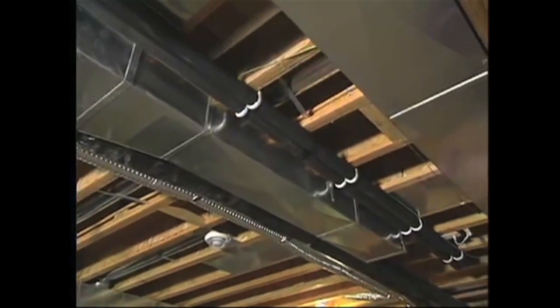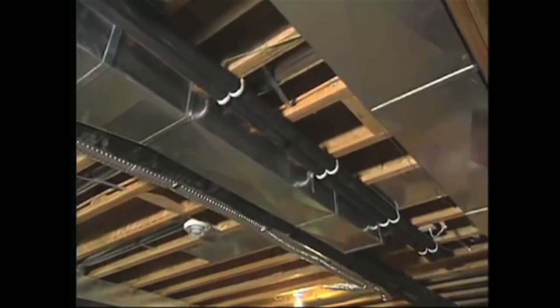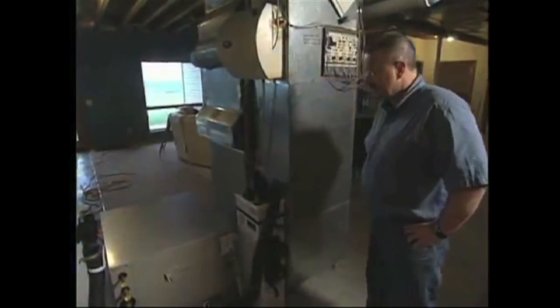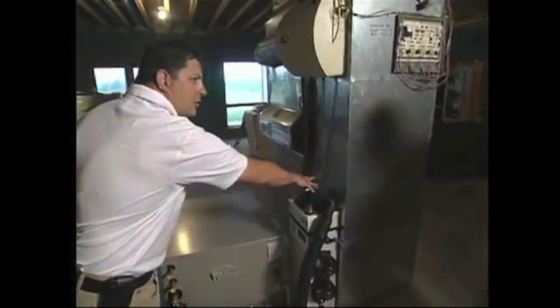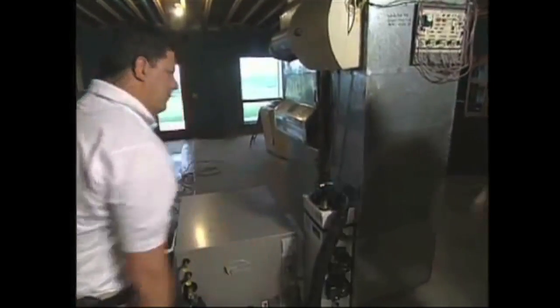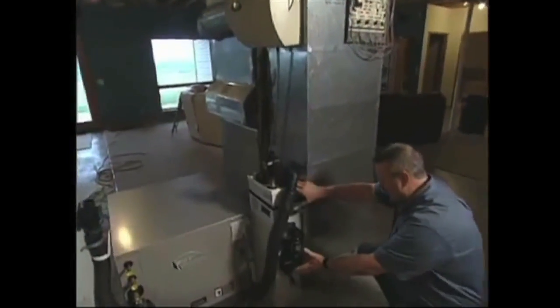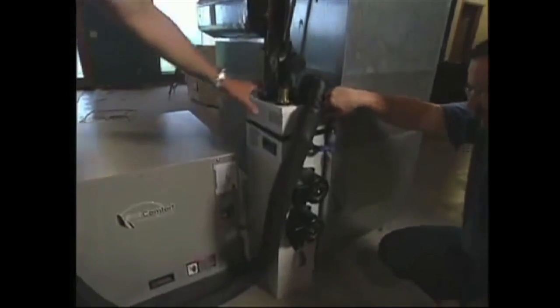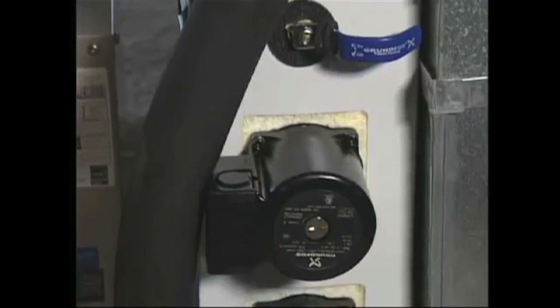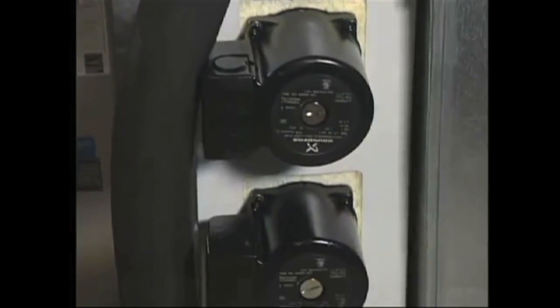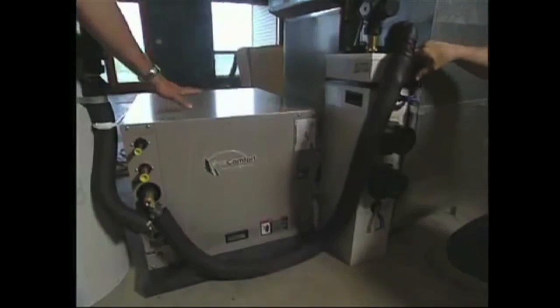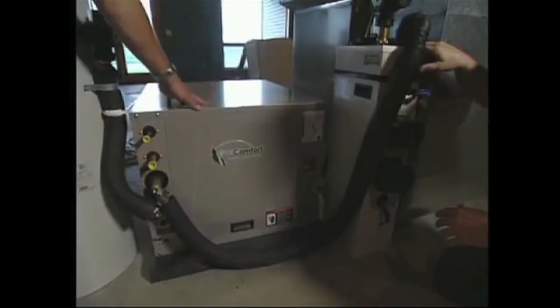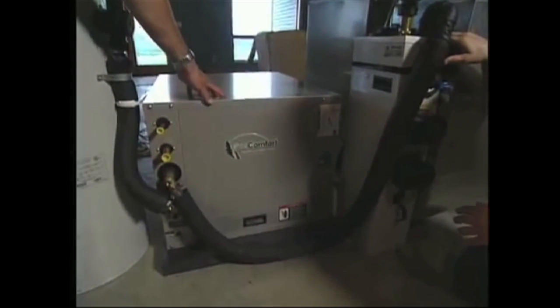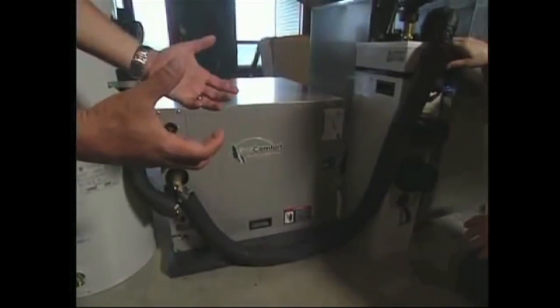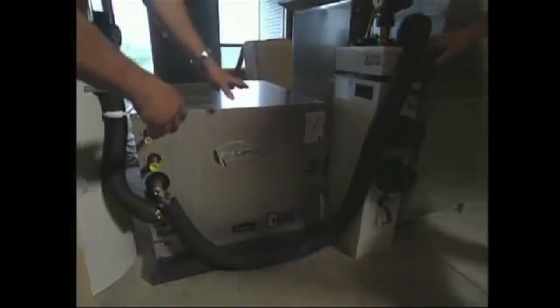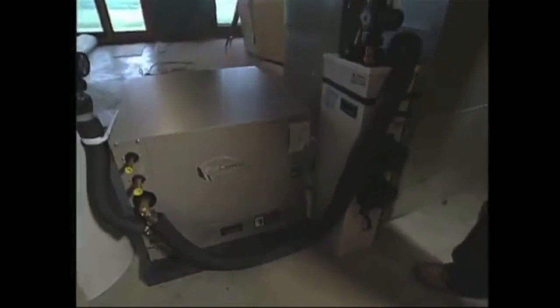I didn't even notice those two pipes there, are they tied into these components? Yeah, one pipe coming in here and one going out. So what am I looking at right here, these would be the circulating pumps? That's right, these move the fluid through the loop field and then through the heat exchanger in the heat pump. And here is the actual heat pump itself, with a compressor inside. This is where we intensify that heat in the heating season and deliver it to the space. Then in the cooling season, we take that energy and put it out to the loop field.